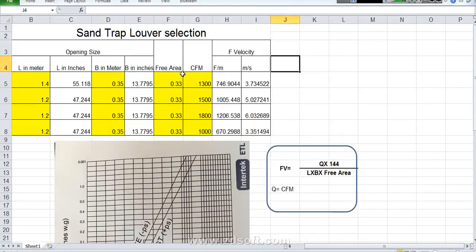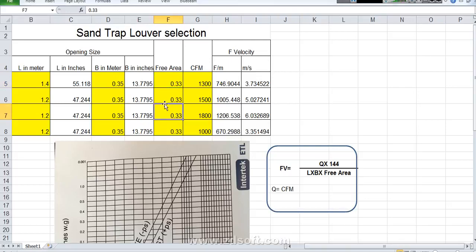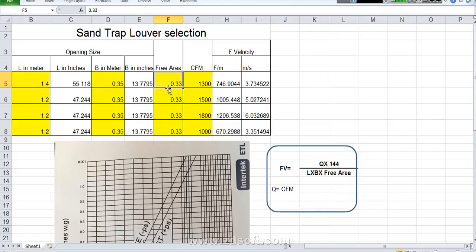For me normally Sand Trap Louver means 33% is there. So we need to mention in this equation 0.33. 0.33 is for my building, as per my concern 0.33 is the free area. So here I mentioned free area.